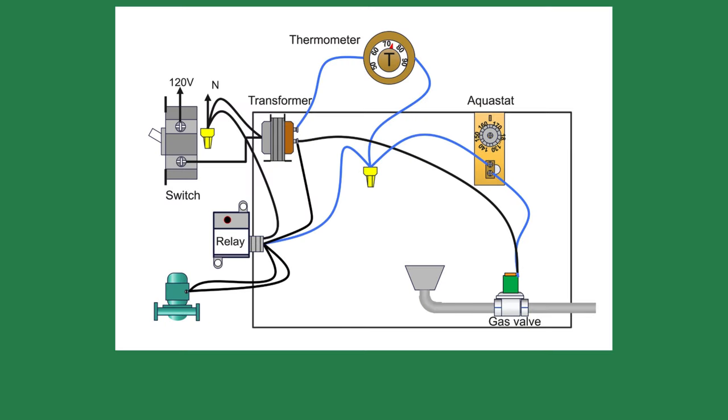Looking at the old boiler, you see it has a standing pilot, which is lit. After removing the boiler cover, you see a transformer and an aquastat set for 165 degrees.